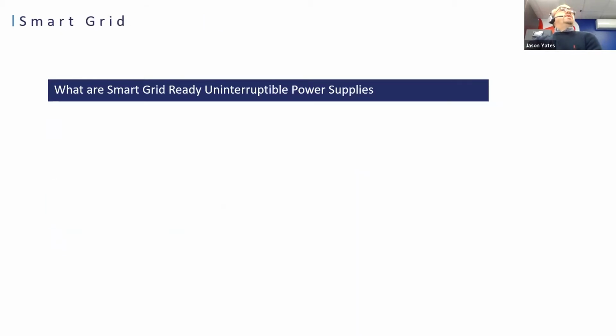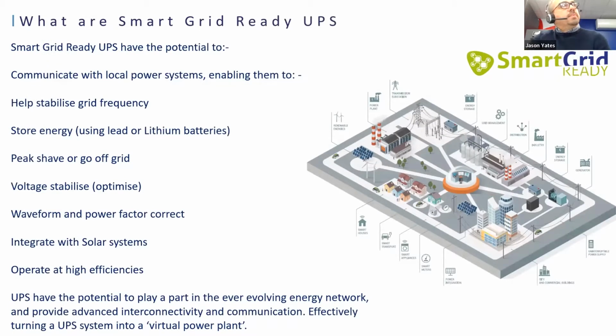So first of all, what is a smart grid-ready UPS system? Well, a smart grid-ready UPS system basically is a UPS that has the potential to, firstly, most importantly, communicate with the local power systems. Therefore, this enables them to potentially help stabilize the grid, and store energy using either lead or lithium batteries. They can peak shave, or they can force the load to go off grid. They can be used to voltage stabilize or optimize. They can be used to waveform correct or power factor correct. They can be integrated with solar systems. Obviously, they need to operate at high efficiencies. Basically, UPS have the potential to play a big part in the ever-evolving energy network and provide advanced interconnectivity and communications, effectively turning a UPS system into a virtual power plant.